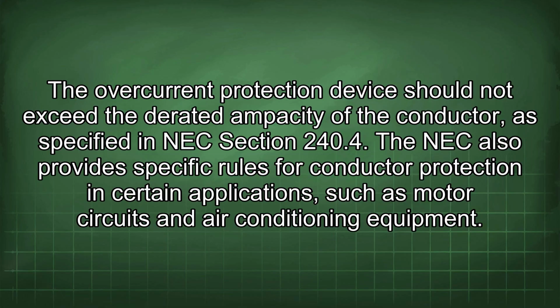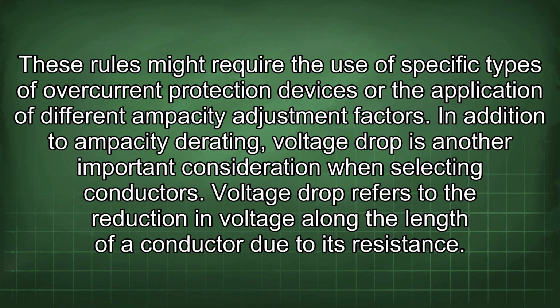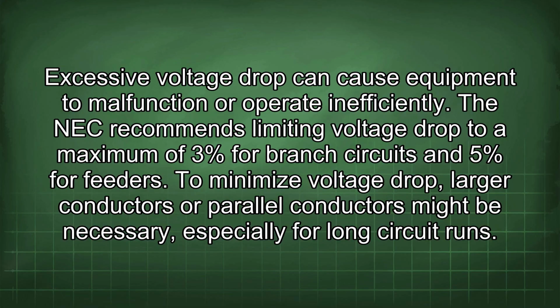The NEC also provides specific rules for conductor protection in certain applications, such as motor circuits and air conditioning equipment. These rules might require the use of specific types of overcurrent protection devices or the application of different ampacity adjustment factors. In addition to ampacity derating, voltage drop is another important consideration when selecting conductors. Voltage drop refers to the reduction in voltage along the length of a conductor due to its resistance. Excessive voltage drop can cause equipment to malfunction or operate inefficiently.